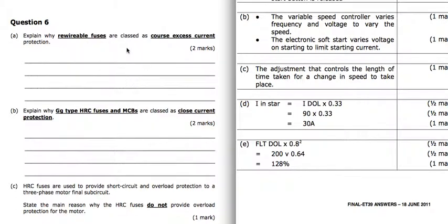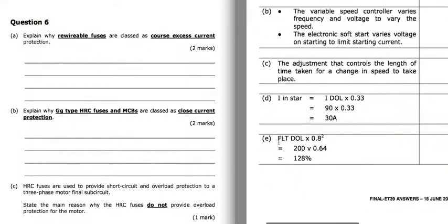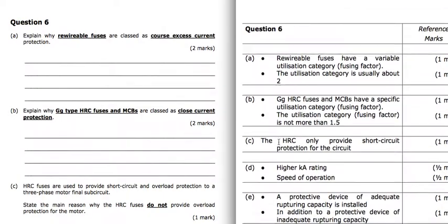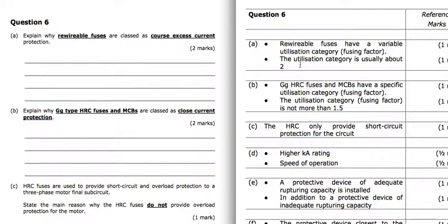Rewirable fuses are classed as coarse excess current protection. They're coarse excess current protection because they don't give us very close protection, basically. They've got a variable utilization category, so that fusing factor is not a determined value. It's very variable, and it's usually around that 2 mark. So if we're talking about a 20 amp fuse, it's not going to blow at 20 amps, it's going to blow at 40 amps with that fusing factor of 2. So it doesn't give very close protection.